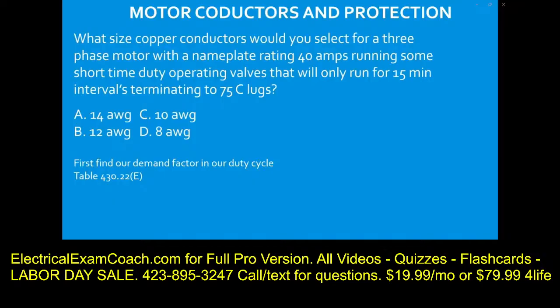So when we find it, we come over and we tee off with our time, which is 15 minutes, and we're going to find a demand factor of 120%. Then we take our original 40 amps, multiply it by 1.20. Now we have 48 amps.